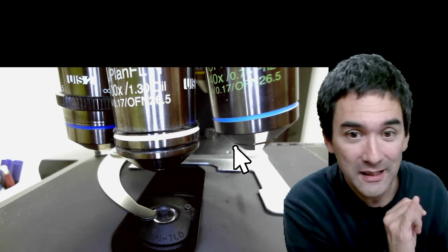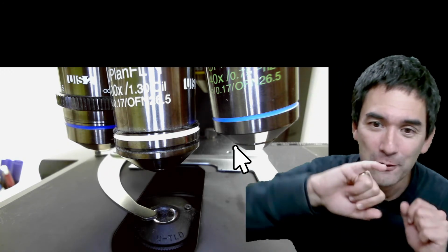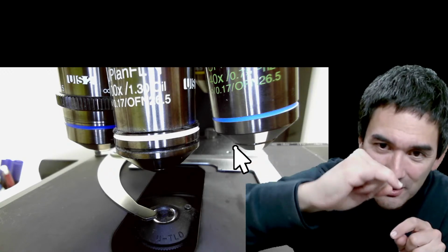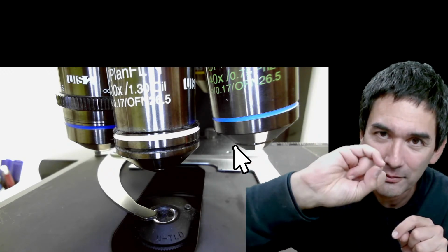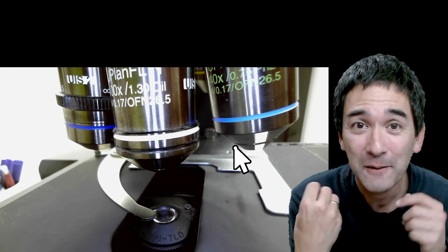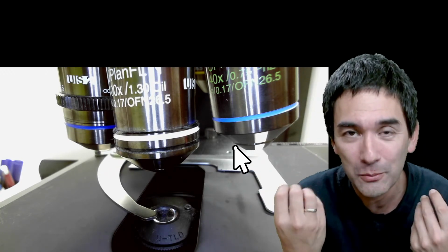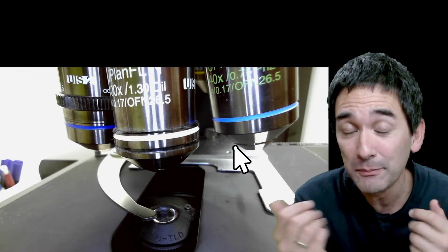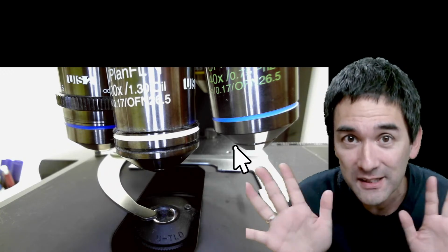My sales representative told me: don't be afraid. Take some cleaning paper and take your fingernail. If there's too much dirt and oil in there, start scratching it out a little bit. He says, don't be afraid. The lenses can actually withstand more than you might think. Many people are afraid of doing that because they're afraid of damaging the lens, but he says that's okay.